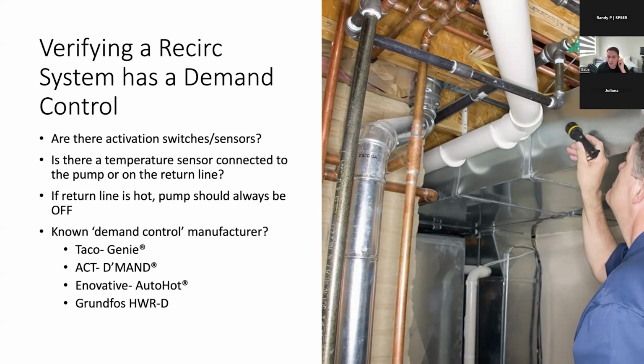So right now, I would say that the most prevalent on-demand systems are the Taco Genie, ACT D'Mand. Of course, we have our AutoHot system. Grundfos has an on-demand system that meets Energy Code. And there's some other ones on the market too. And then you want to verify that there's some type of an activation switch at the point of use, either a push button activator or a motion sensor, or it could be a flow switch that's built into the plumbing itself. We've seen systems out there that use a little flow sensor that anytime someone turns on hot water, that flow is the demand sensor that turns the pump on.